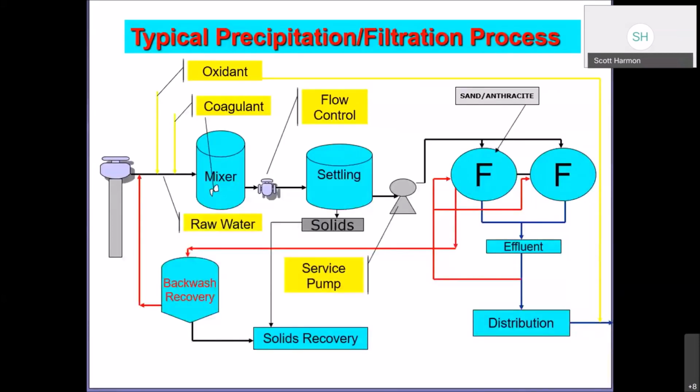So here's a typical layout. And again, I don't know how easily it'll be for people to see. Typical treatment layout for what one of these facilities could possibly look like. So you can see the incoming water. It's hit initially with the oxidant, then the coagulant mixed together. All right, so you have your standard settling and floc situation, and then you have your filters at the end. You have backwash recovery, solids recovery.